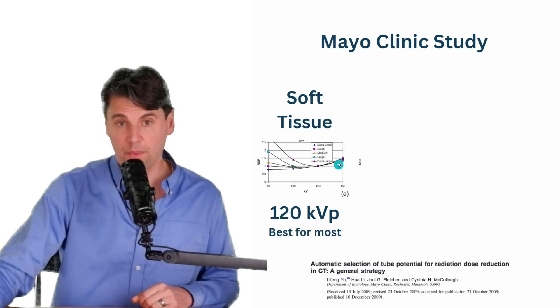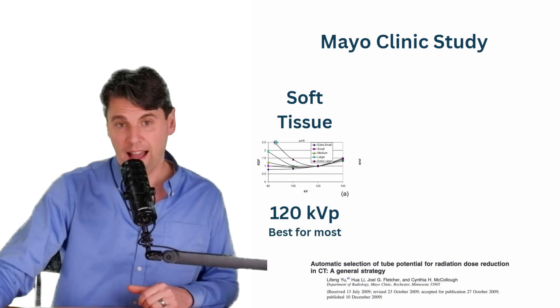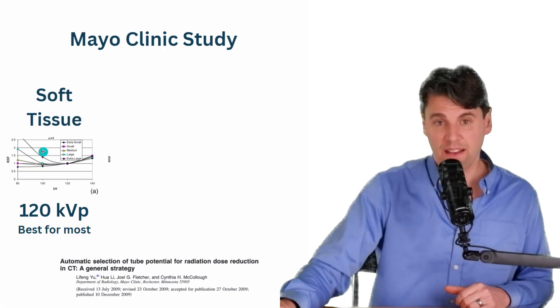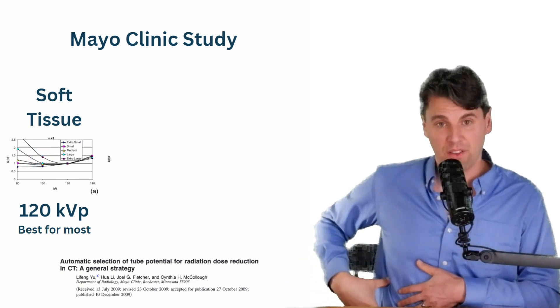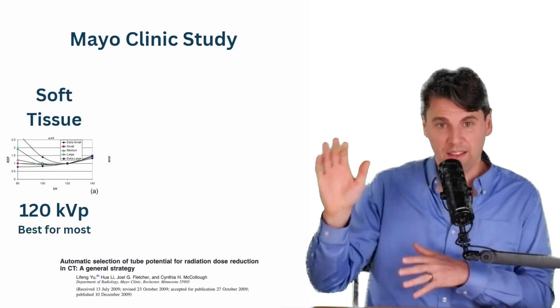For the soft tissue task, you can see the curves are more flat. But for relatively larger patients, it becomes actually disadvantageous to use the lower KVPs, because those lower KVPs are not able to adequately penetrate. You can see there is significant difference here, based on the patient size. That's why we need a method to actually estimate the patient size, and use that in this selection.